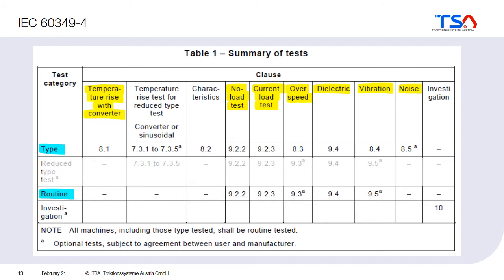The standard tells us which kinds of tests should be done. First, there is a temperature rise test with a converter, which we will discuss on the next slide. Then, to confirm electromagnetic performance, you do a no-load test and a current load test, which are also part of the routine tests. To confirm mechanical integrity, you do an overspeed test. To check the insulation, there is a dielectric test. And of course you must also check the machine for vibration — measuring vibration velocity — and also for noise.